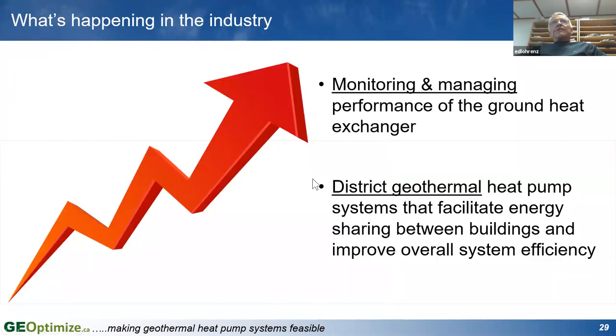So the other thing that I wanted to talk about a little bit is some of the things that are happening in the industry now. There's a number of things that are helping to make this system better. One of the things being developed is a way to monitor how much energy is being pushed into the ground in real time versus how much is being pulled out of the ground. That's done by adding an energy meter to the ground heat exchanger. How many BTUs are you trying to shove into the ground? How many are you pulling out on an annual basis? And what does that do to the temperature of the ground?